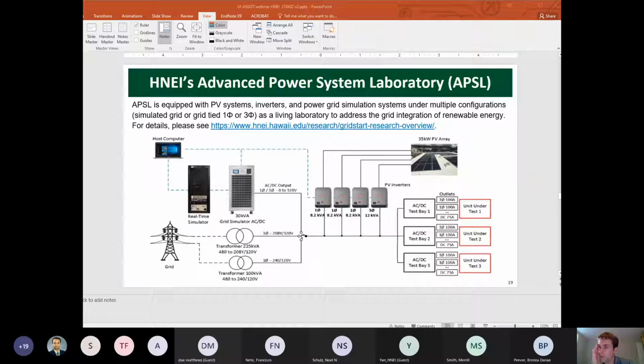Okay, so the voltage rise issue, question number one, Yan maybe is best situated to talk to that. She looked at it specifically. Voltage does get affected, but do you have a few comments on that, Yan? Yes, for sure, with different capacity of the solar PV, we see the voltage rise issues. So some research focused on the smart PV inverter control, which can improve the voltage rise issues. But in general, only a subset of the load is able to follow the curve, right? Certain appliances now are maybe more controllable, water heaters and some other things, but for the large part, your load's not going to follow your PV.